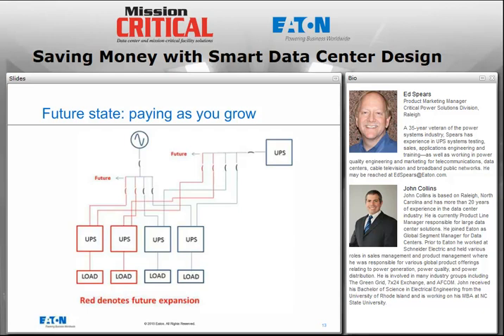Is UPS distribution to the critical load single path? It is single path in this case, but remember that you do have the ability to operate the primary UPSs as a dual bus architecture. In other words, I can pick two of them and say I want one of you to be side A and one to be side B. In that case, you would be out of the single path and back into the dual path. The client also has the ability, not to overcomplicate things, but they can take the path out of the UPS and then split it in two and do all the distribution from the UPS downstream as a dual path, even though they really only have one UPS supporting it. That's just an alternative.